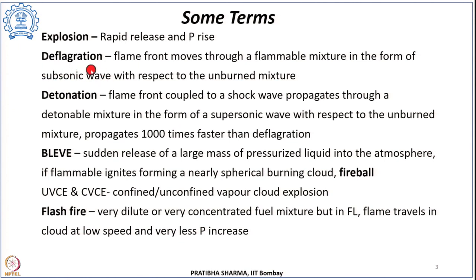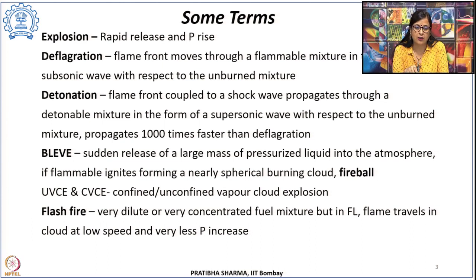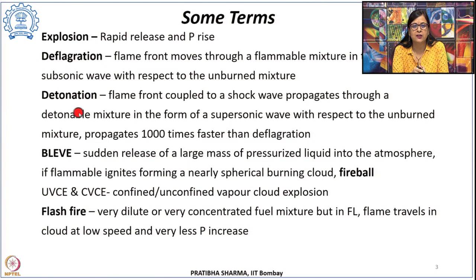Deflagration refers to the process where the flame front moves through a flammable mixture in the form of a subsonic wave, with respect to the unburned mixture of hydrogen and the oxidant. Detonation is where the flame front, coupled with the shock wave, propagates through a detonable mixture in the form of a supersonic wave. Detonation causes much more devastation compared to deflagration and propagates 1000 times faster.